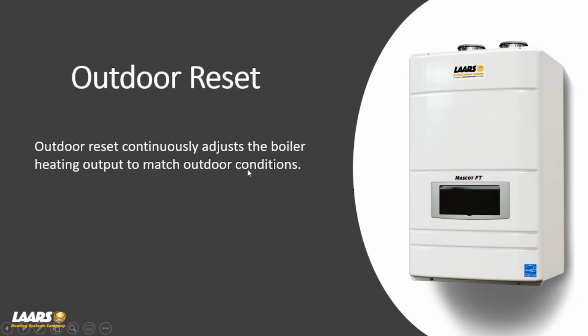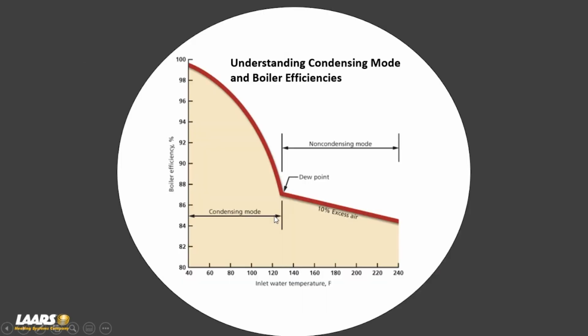So outdoor reset continuously adjusts the boiler's heating output to match outdoor temperature. So here we're showing basic inlet temperatures, outlet temperatures, and condensing mode. So here's our inlet water temperature back to the boiler. So example that I used, 180 supply and returning at 160. Over here is boiler efficiencies. We're showing efficiencies from 80 to 100%. ASHRAE handbook, which is what this chart is going to base this on, 10% of excess air. What is that? That is your air and fuel mixture before firing. So I mentioned a mixing station. That's where your propane or natural gas orifice would be. That's your air fuel mixture right there. So they base that at 10%. And at 10%, the dew point, that's your condensing dew point, they're going to tell you is 130 degrees.